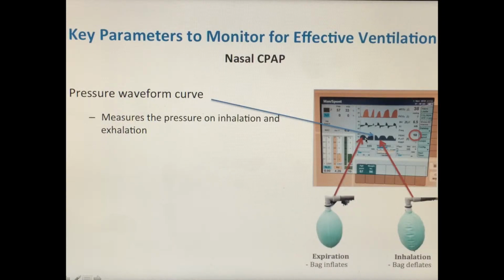The dip, as seen here, this is signifying that there is a loss of pressure within the system. That is because the patient is taking a negative breath, and you will also see that the anesthesia bag at this time will slightly deflate. As soon as the patient exhales again, you will notice that the pressure goes back up. This also shows us that a continuous positive airway pressure is being maintained since the dip never goes to zero.